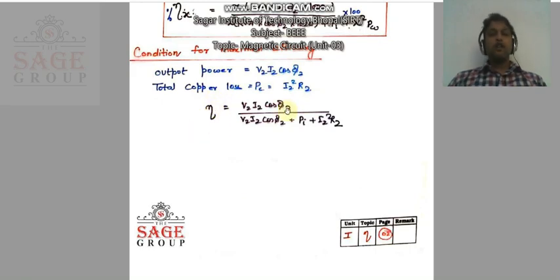So whatever first derivative of the efficiency you get, you equate that value to 0, and when you solve this equation, you find that the core loss Pi becomes equal to I2 square R2. From here, after doing all this, you get a final equation: core loss equals copper loss. It means for getting the maximum efficiency condition in your transformer, you have to put core loss equal to copper loss, or copper loss equal to core loss.